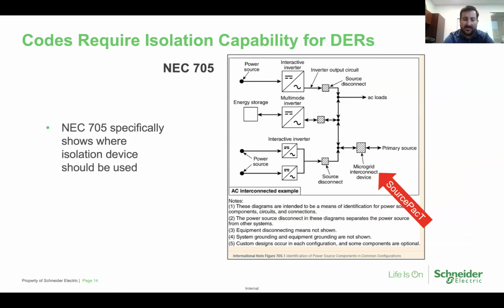Again, this diagram is an excerpt from the National Electric Code, and it shows here they call it the microgrid interconnect device, isolation device. It means the same thing, and they're all synonyms. But you can see how it's being fed by numerous inverters, which could be your battery energy storage system, can be your solar, on the left-hand side there. And those are serving as resiliency when there's an outage, but also bringing down your energy costs when you're tied to utility. And then on the very top right-hand side, you can see the AC loads, which basically are your critical loads that are being fed. So if that disconnects, it disconnects everything except your critical loads from those inverters, and you're good to go. Next slide.